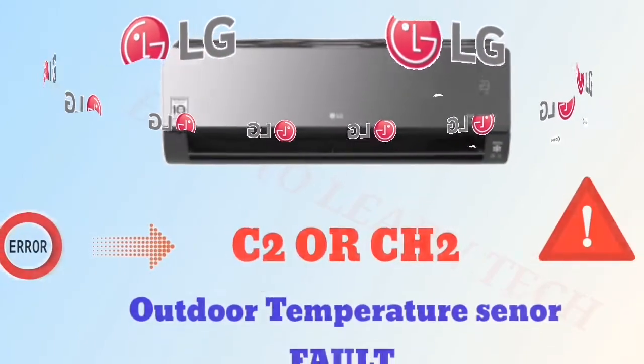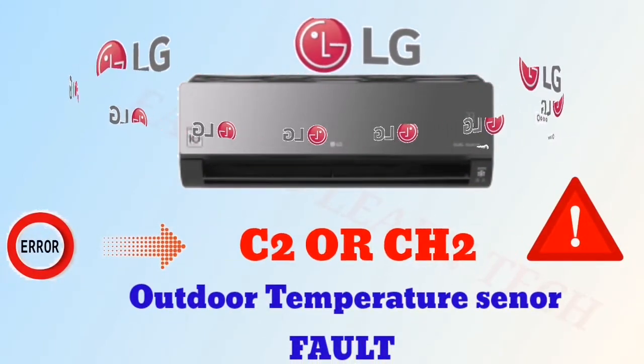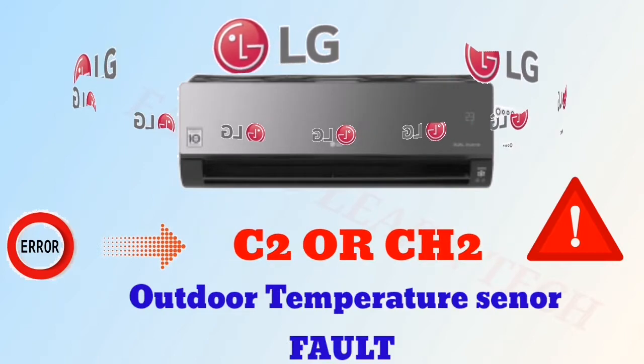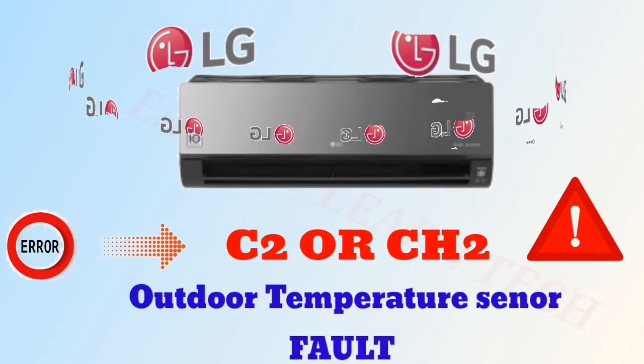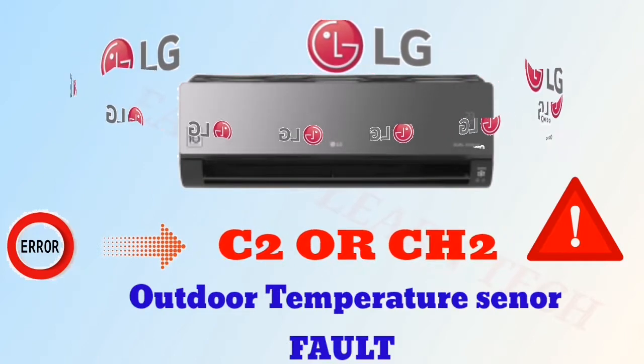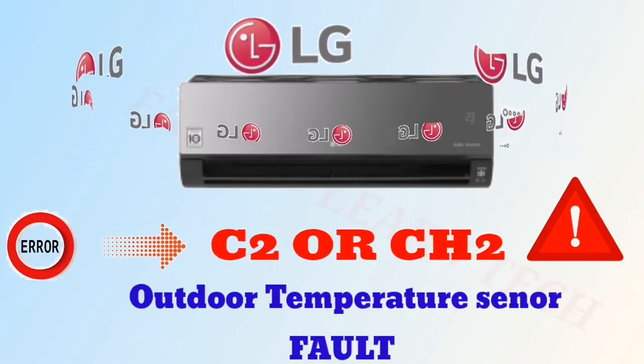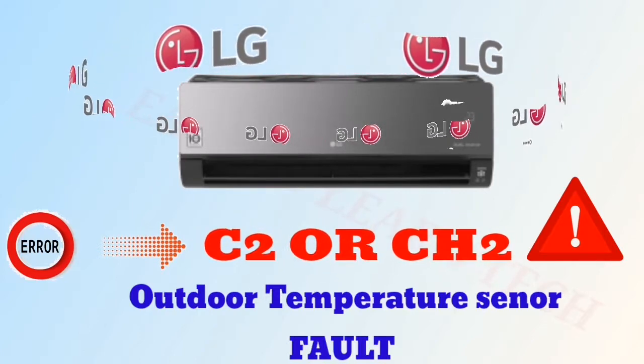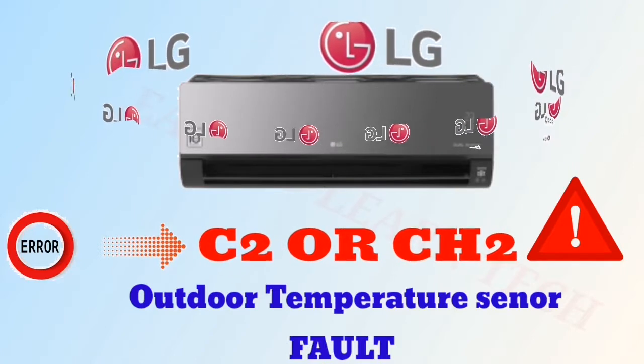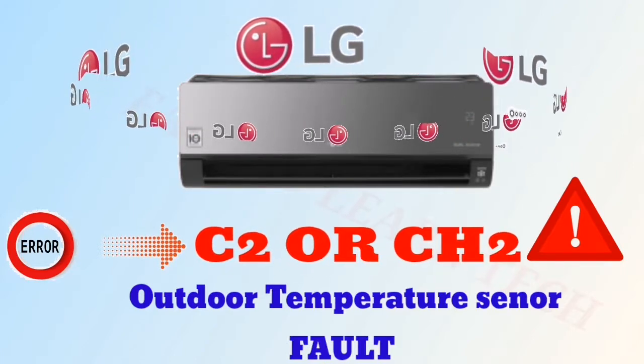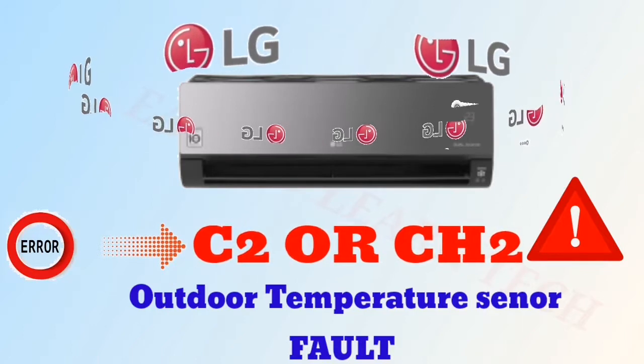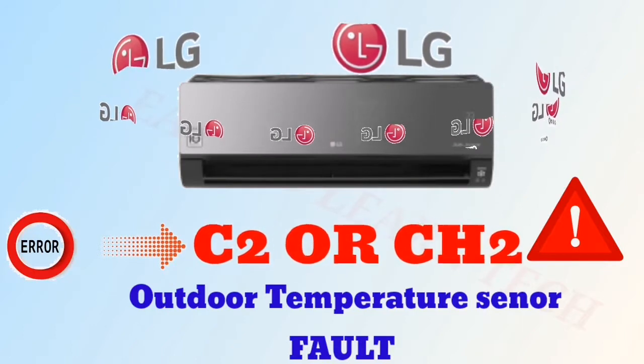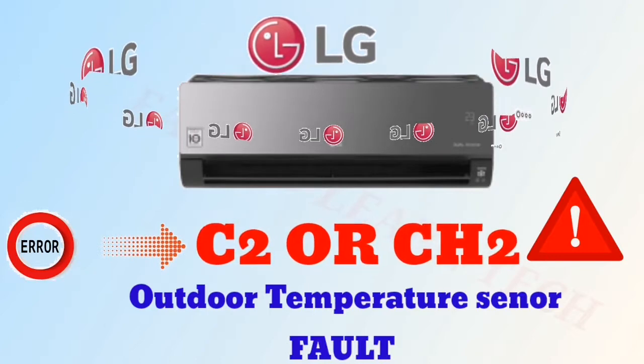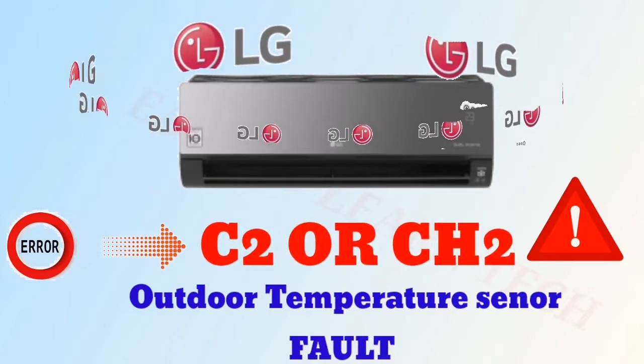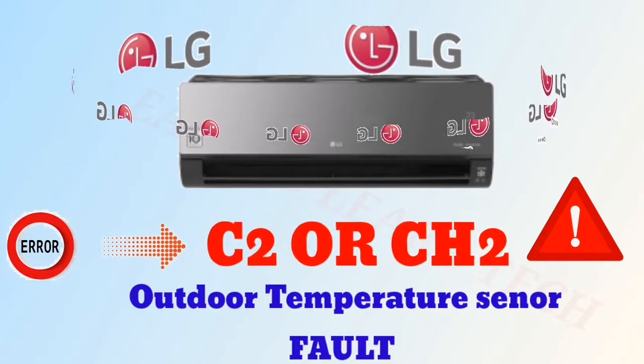Let's check the next error code, C2 or CH2. When you get an error display on your outdoor unit, it means the outdoor temperature sensor is faulty. This sensor is installed just at the back side of our condenser coil. First you have to check the placement. If the placement is good, then you have to check the resistance of the sensor, and if the resistance is also good, then you have to check the PCB, whether the output power for the sensor is coming from the PCB or not. If the output power is not coming, then you have to change the PCB, and if the resistance of your sensor is not perfect, then you have to change the sensor, and your unit will be working.